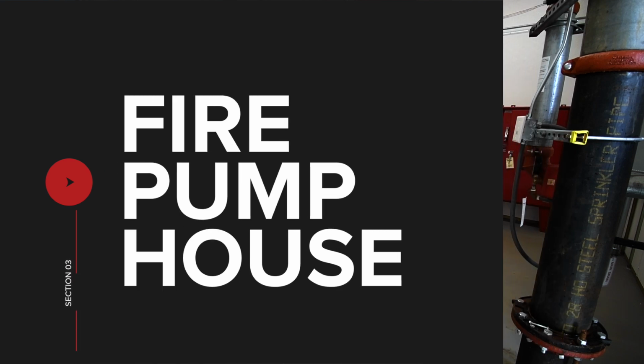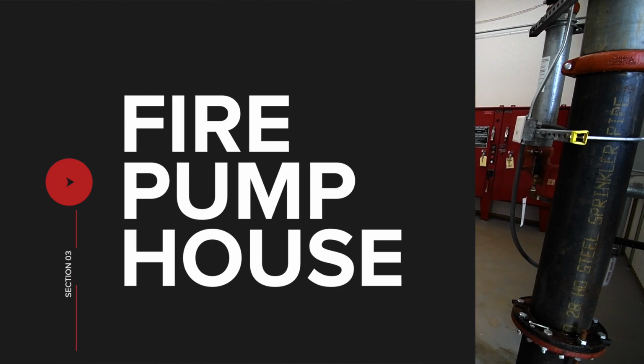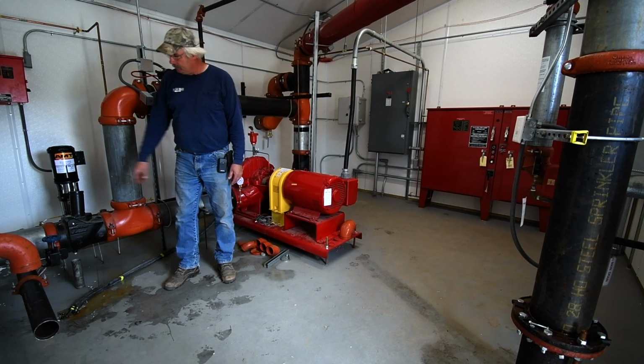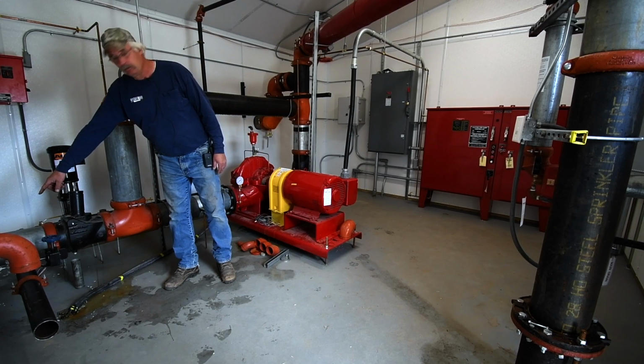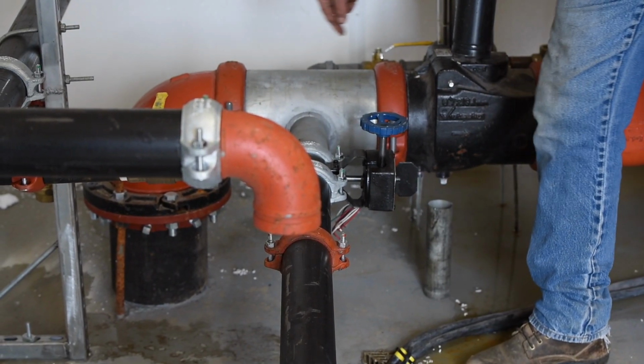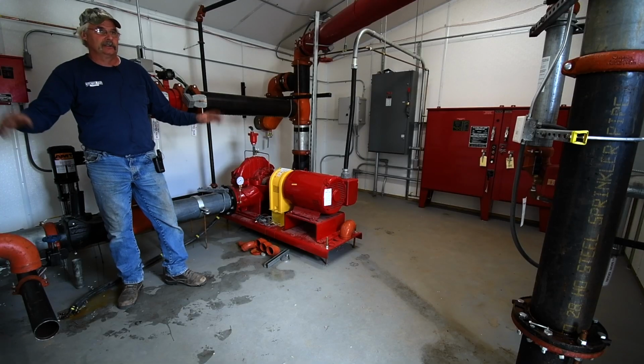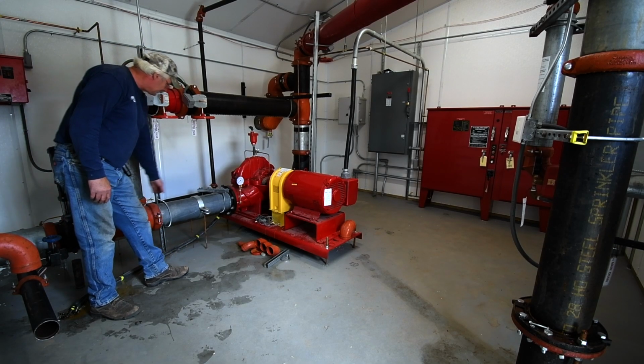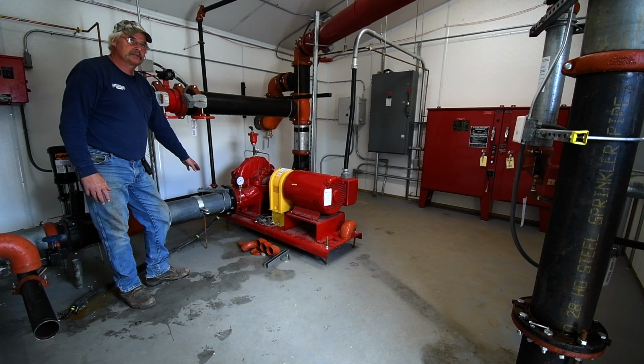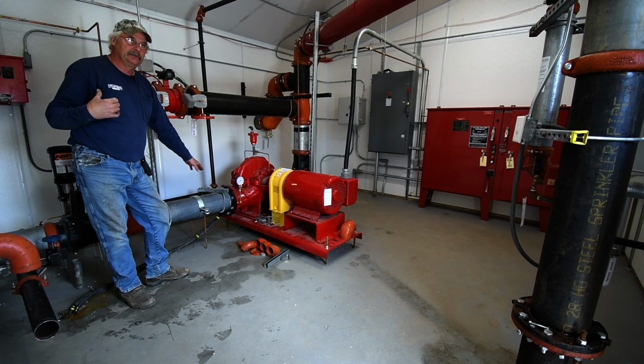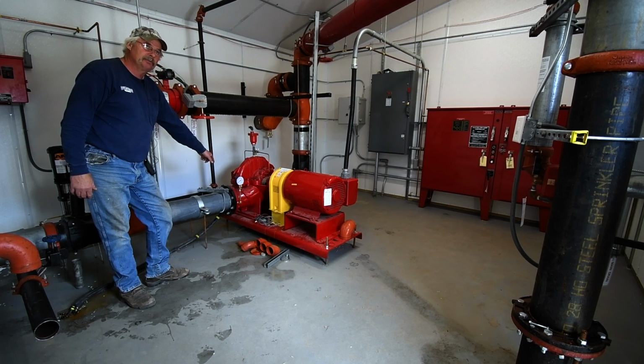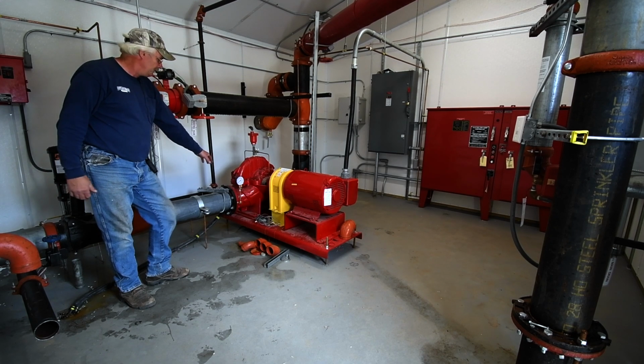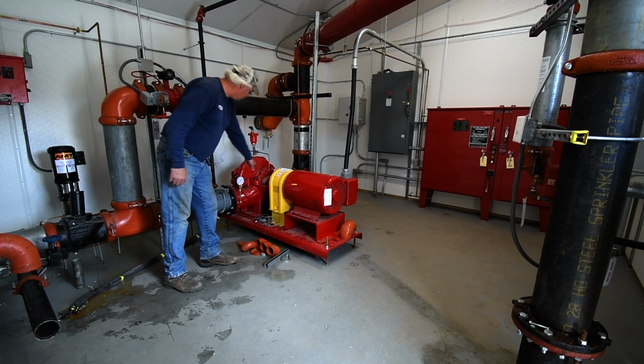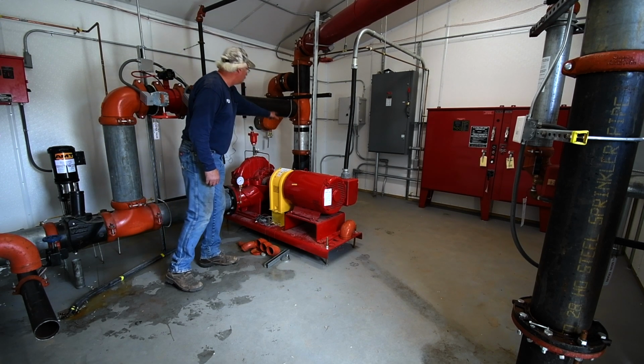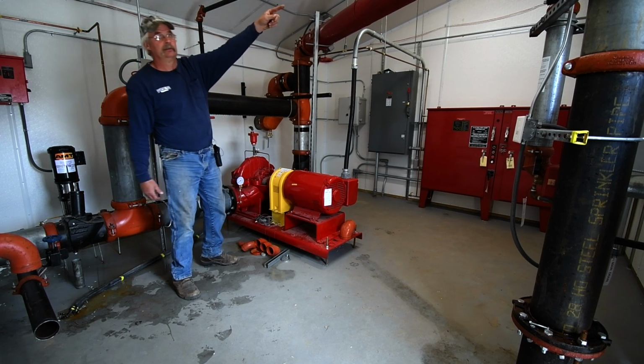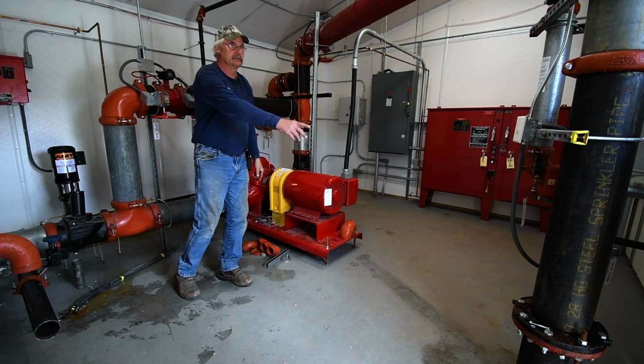What we're working on now, we're in the north fire pump house, the new fire pump. And basically what we have here, we have an 8-inch underground coming in here, right over here, and it comes up and it comes into your system, which feeds the entire facility. So what that does, it comes across here, and right now they're doing some work on the tank out there, so we have packing on our fire pump that's dripping over, that we don't have any pressure on the suction side. So the water is going to come into the fire pump, turn, go up, go right over, head here, and down into your systems.